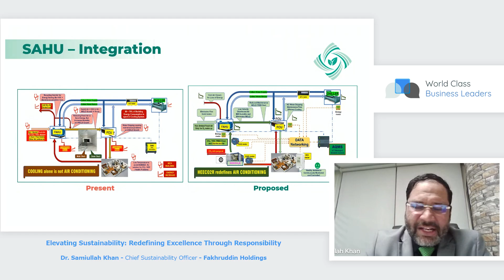And not only just air, we bring in air which is extremely pure. In terms of CO2 level, we bring in about 0 ppm CO2 level, 0 to 10 ppm max, and we take the air to about minus 70 to minus 100 degrees dew point to remove the humidity. So this is the system which we operate.